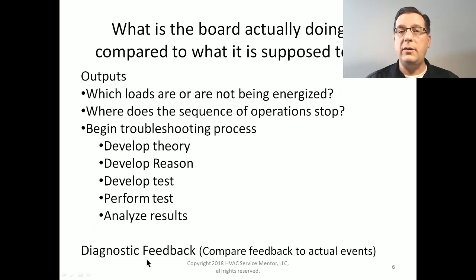Now, a lot of control boards are going to provide diagnostic feedback. The diagnostic feedback could be in the form of a flashing indicator light. It could be in the form of a code. It could be in the form of an LCD display that tells you things. One of the most important things to realize about diagnostic feedback is that it's not perfect. It can't account for every possible situation. It doesn't necessarily know that a plastic bag has been sucked up onto the intake pipe. All it knows is that the pressure switch isn't closing, and that's what it's going to tell you. It's up to you to go and find the plastic bag.